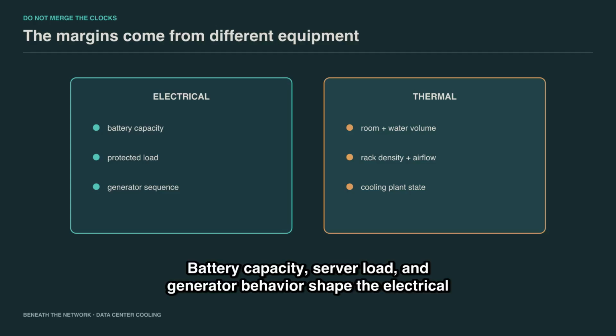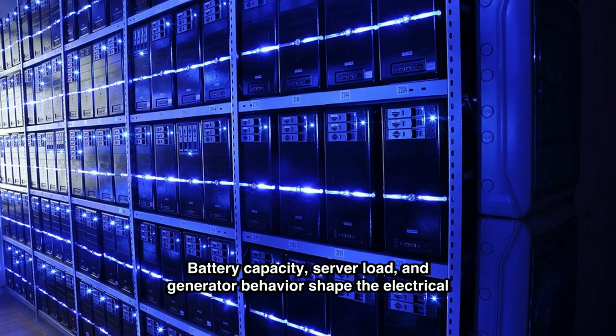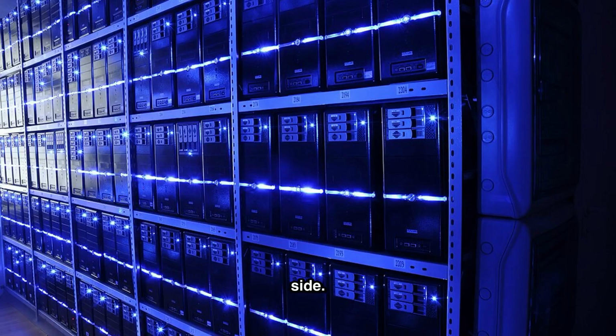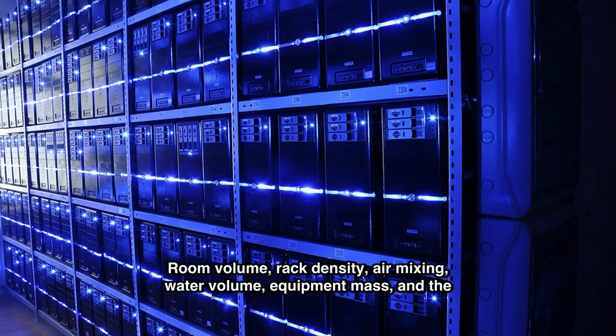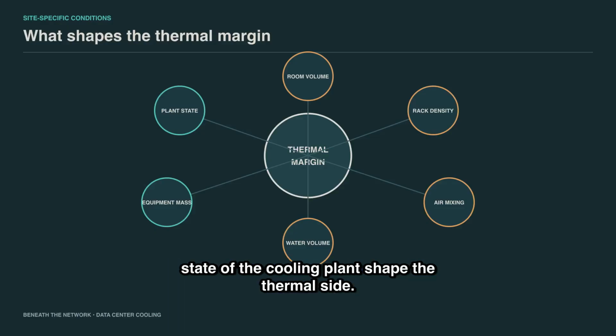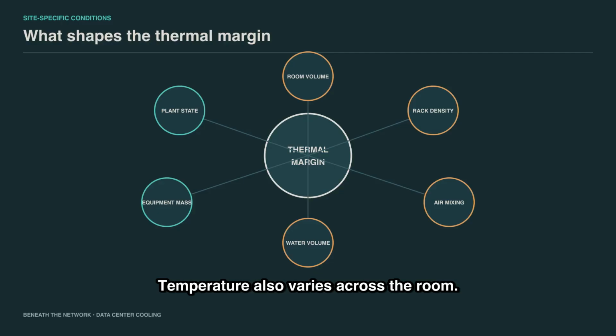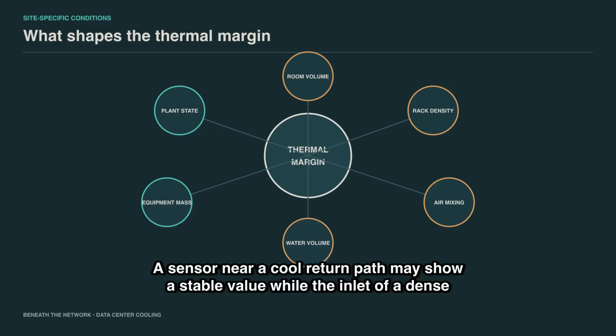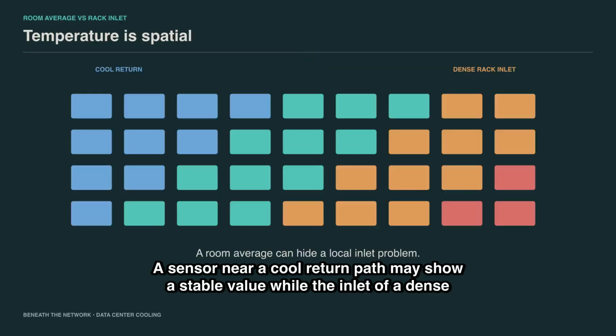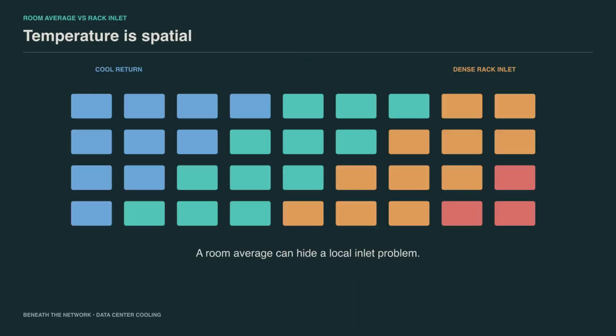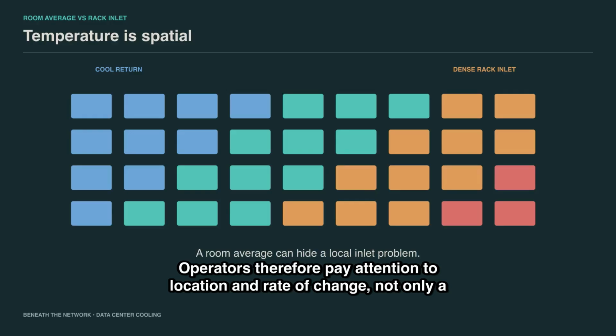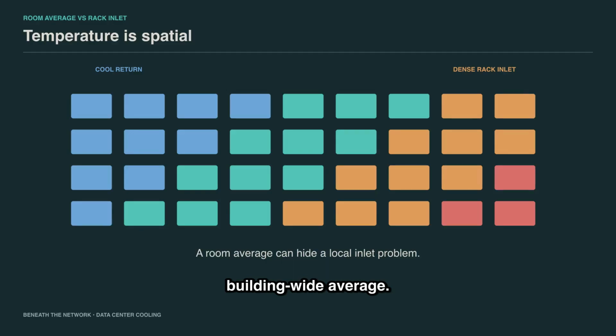Battery capacity, server load, and generator behavior shape the electrical side. Room volume, rack density, air mixing, water volume, equipment mass, and the state of the cooling plant shape the thermal side. Temperature also varies across the room. A sensor near a cool return path may show a stable value, while the inlet of a dense rack is warming. Operators therefore pay attention to location and rate of change, not only a building-wide average.